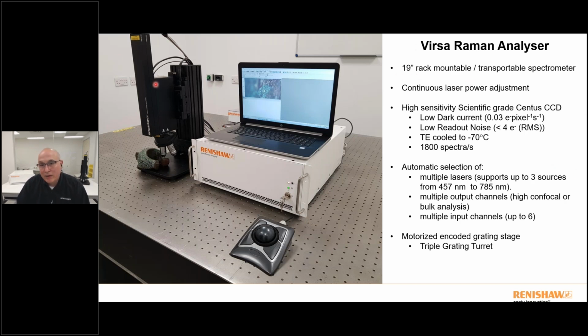This is a 19-inch rack mounted system. We have continuous laser power adjustment, and that laser power is defined as what the sample is actually seeing. It's using the same Renishaw Centrus CCD camera that we put in our inVia, which is a high sensitivity scientific grade system. And we can collect with that CCD camera 1,800 spectra per second, so it's fast. We have the ability to automatically switch between multiple laser sources. As standard, we have 532 and 785 as options, but we have the ability of accommodating other laser sources as well.